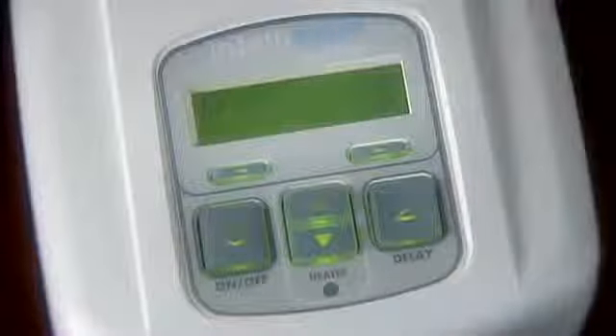If you are using the comfort delay feature with a standard model, airflow at the beginning of therapy is temporarily lowered to a pressure setting selected by your physician when the device was set up. Simply press the delay button to activate this feature. In the final 10 minutes of the delay period, the pressure will gently rise to the pressure prescribed for your therapy. You can repeat the comfort delay cycle by pressing the delay button again if you have not fallen asleep during the initial delay period.